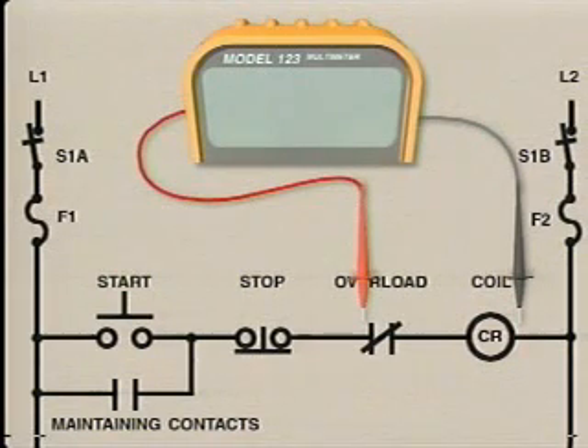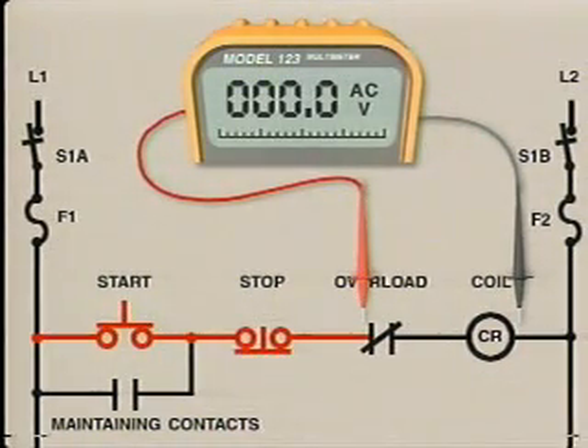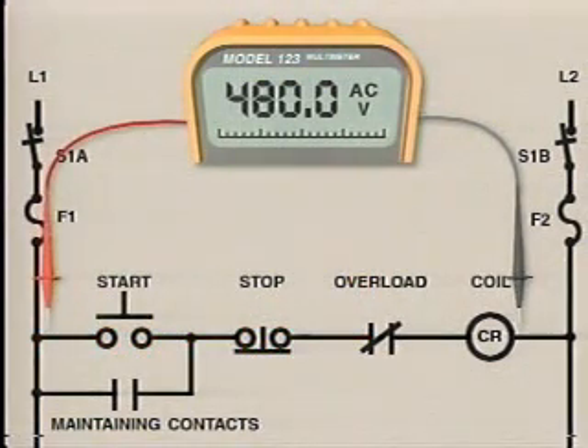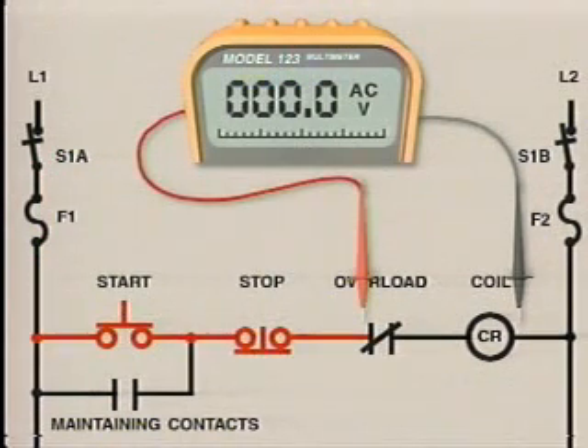The electrician presses the start switch and reads 0 volts on the voltmeter. He verifies that the voltmeter is still operating by measuring the phase-to-phase voltage in the control cabinet. The reading of 0 volts indicates that voltage is not getting to the overload contacts. This means that the problem is in the left half of the circuit.